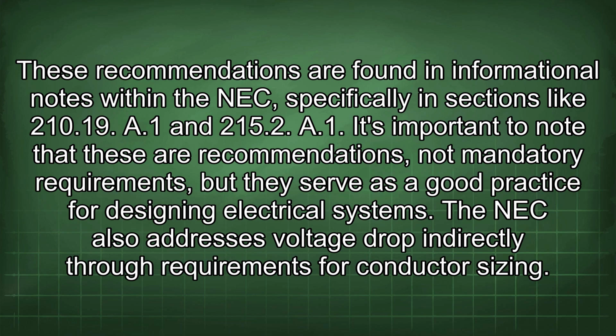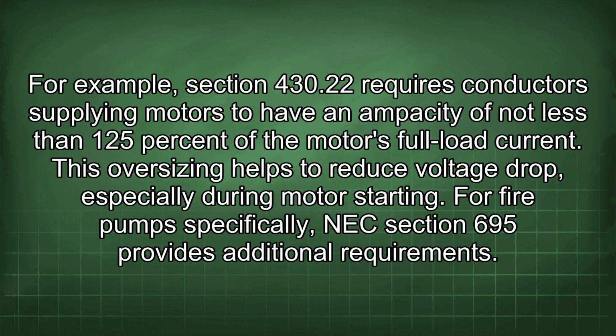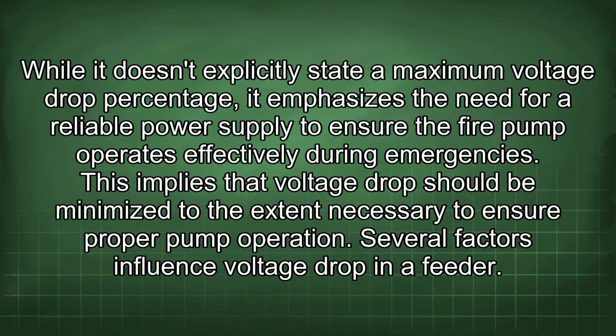It's important to note that these are recommendations, not mandatory requirements, but they serve as a good practice for designing electrical systems. The NEC also addresses voltage drop indirectly through requirements for conductor sizing. For example, Section 430.22 requires conductors supplying motors to have an ampacity of not less than 125% of the motor's full load current. This oversizing helps to reduce voltage drop, especially during motor starting. For fire pumps specifically, NEC Section 695 provides additional requirements. While it doesn't explicitly state a maximum voltage drop percentage, it emphasizes the need for a reliable power supply to ensure the fire pump operates effectively during emergencies. This implies that voltage drop should be minimized to the extent necessary to ensure proper pump operation.